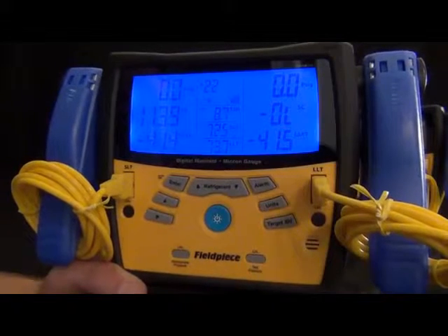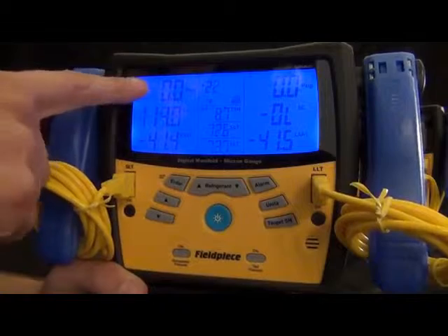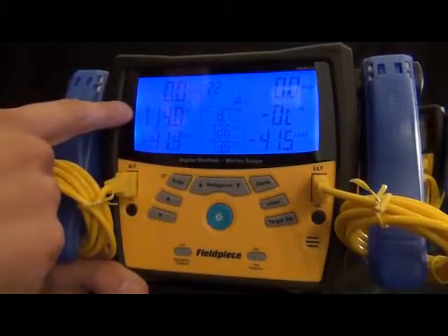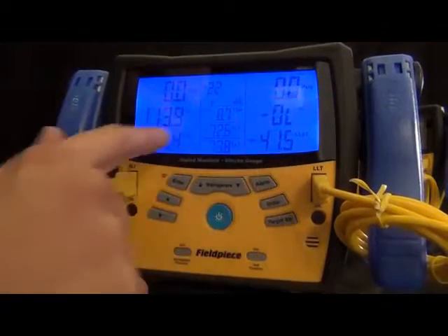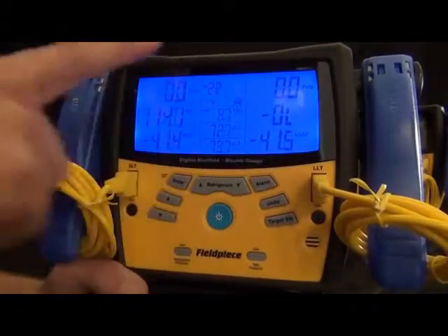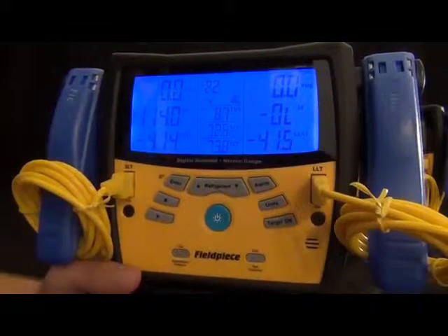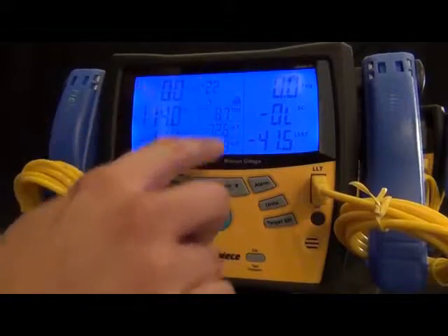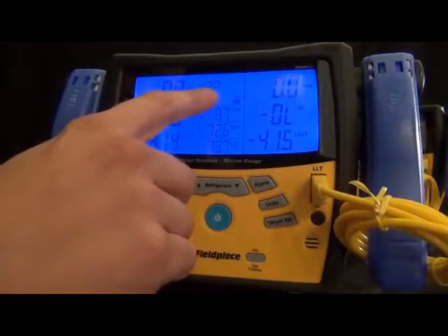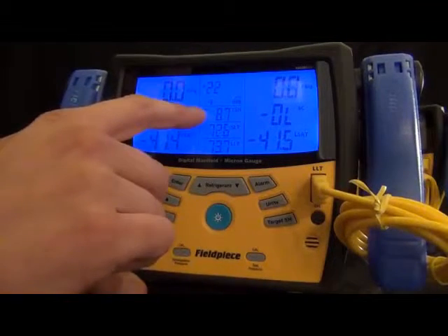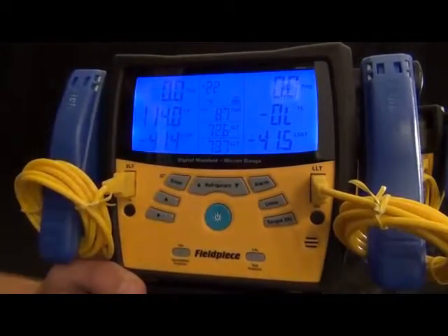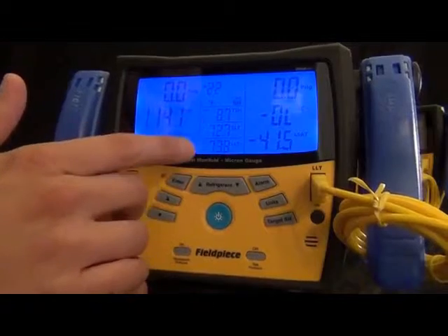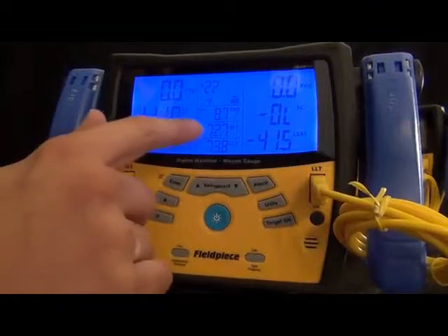So you'll first see that we got the pressures on the top line, we got the superheat and subcooling on the middle line, and then we got V-SAT and L-SAT on the bottom line. The left side is for the low side, and the right side is for the high side. Now down the middle column we have the refrigerant that you're using, the target superheat mode, and that's the only extra mode that you ever have to go into. Everything else that it's measuring is just displayed right here. Then we got suction line temperature and liquid line temperature.